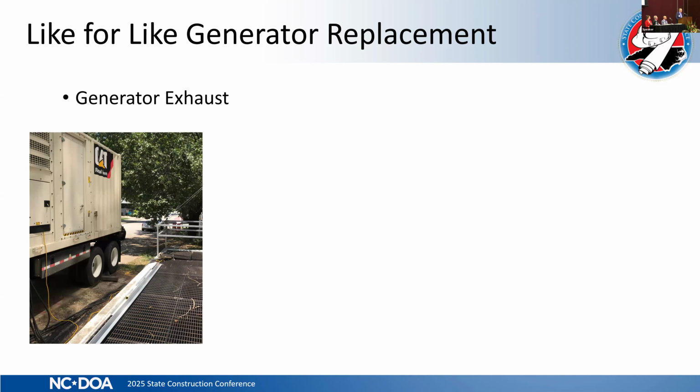So the rental generator was sitting basically on the sidewalk outside, and from the room, the exhaust left the room above the generator and went out into an areaway. But the exhaust vent turned down into a pit in that areaway, and the exhaust would then rise up through the metal grate, as you see there, and it would cool in that process, to a certain extent.